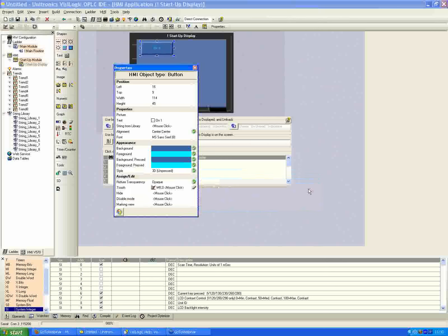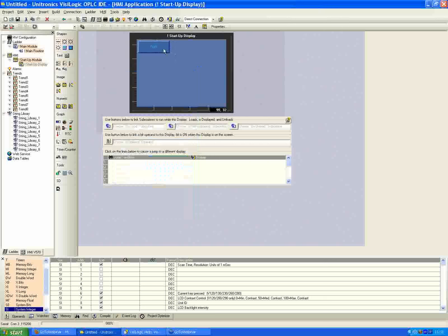I'll hit OK. So now we've defined our text called 'On 1', and assigned a link property of MB0. That's really all we need here. The other parameters — hide, disable, marking view — when clicked, each will ask you to assign another Boolean memory bit. If that bit is high, it will hide the variable, gray it out in disable mode, or add a highlight background in marking view. These are more advanced parameters you can link to a password, for example, which we'll look at later. For now we can close out and our parameters will be saved for on button 1.